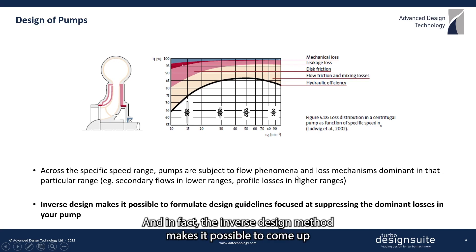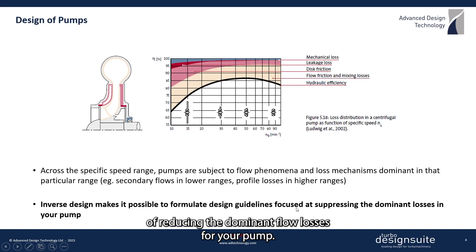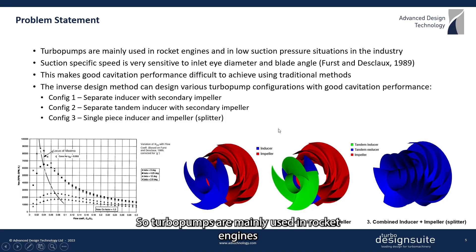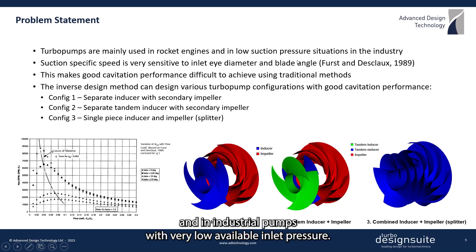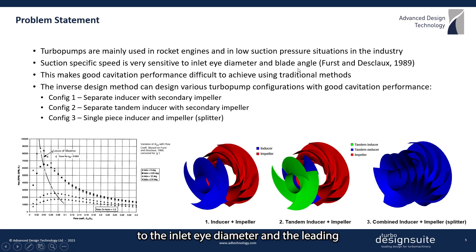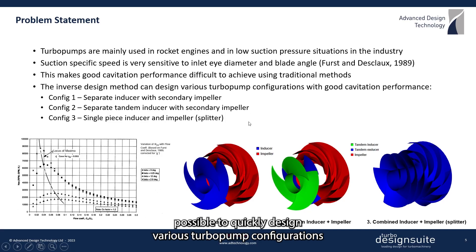The inverse design method makes it possible to come up with a set of optimal design guidelines based on fluid dynamic considerations of reducing the dominant flow losses for your pump. This brings us to our problem statement. Turbopumps are mainly used in rocket engines and in industrial pumps with very low available inlet pressure. Because the suction specific speed is very sensitive to the inlet eye diameter and the leading edge blade angle, this makes cavitation-free performance difficult to achieve using traditional methods. Using the 3D inverse design method, it's possible to quickly design various turbopump configurations under industrial time scales and with good cavitation performance.